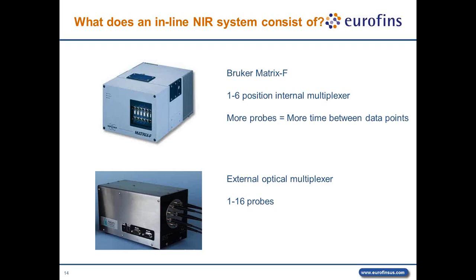For example, the Bruker Matrix F is a built-in multiplexer that can accommodate up to 6 probes at once. If you have interest in more than 6 fiber optic probes, there is the option of an external multiplexer, some of which can accommodate 10 to 16 fiber optic probes. In a multi-probe inline system, the cost of each additional probe is in the time that it takes to complete a cycle through all the active probes.